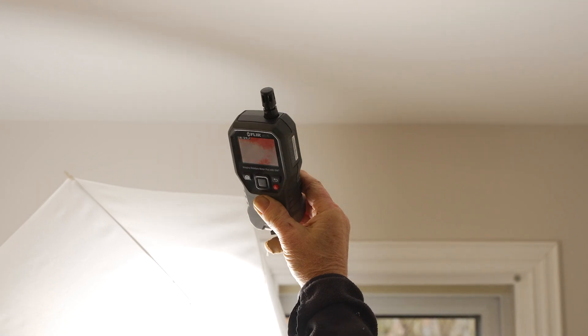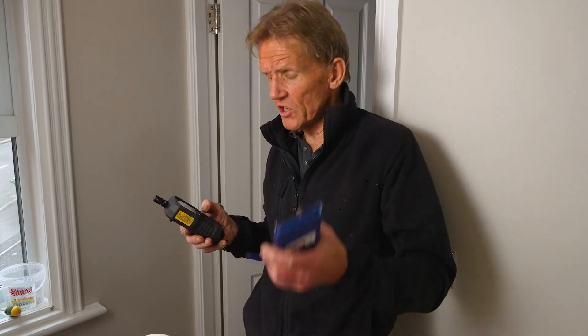If you're thinking of using one of these thermal imaging cameras - you can hire them or buy the cheaper one - it's a good idea to do it on a cold day, maybe in the morning. Have the house heated for two or three days properly, with the heating on as you would normally. Then on a cold morning go around and take the readings, because that gives you the biggest contrast and you'll see where the thermal bridges are. As soon as the sun comes out and warms one of the elevations, the reading won't be as dramatic.